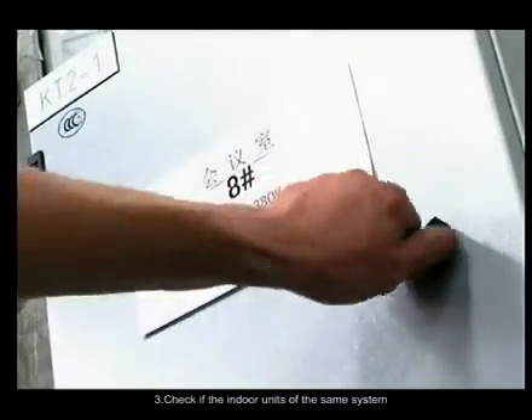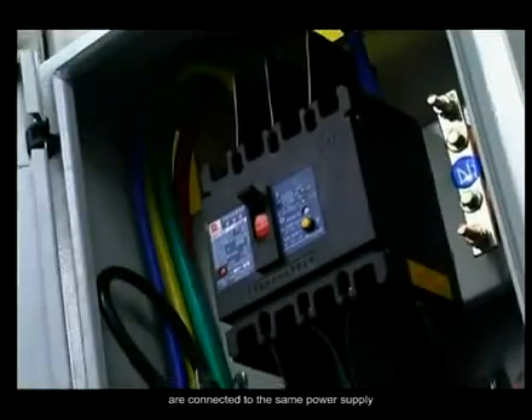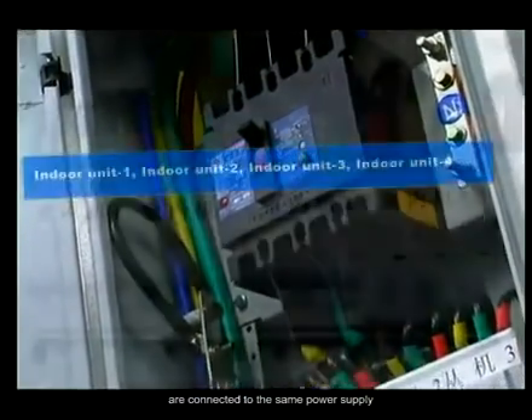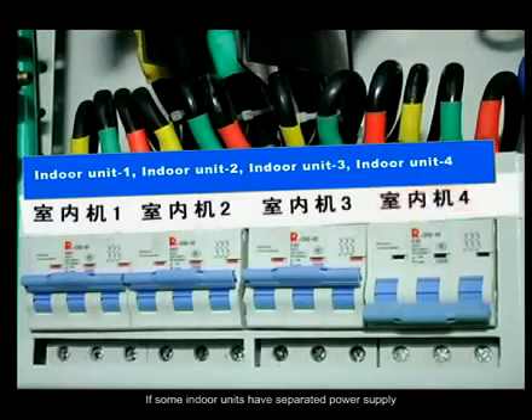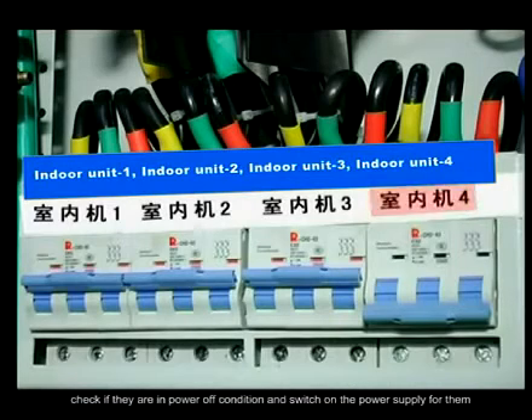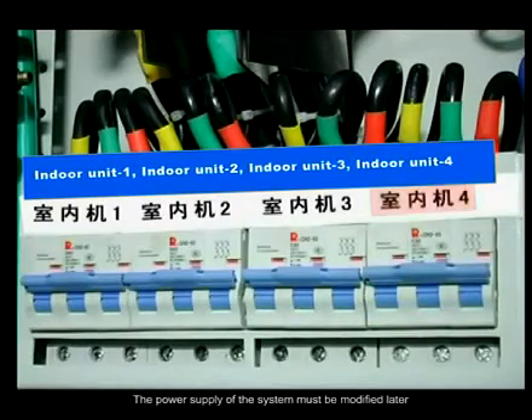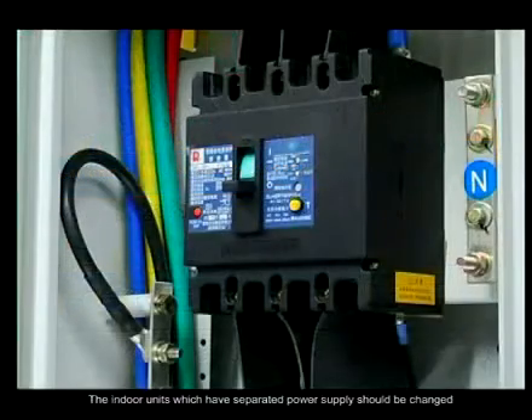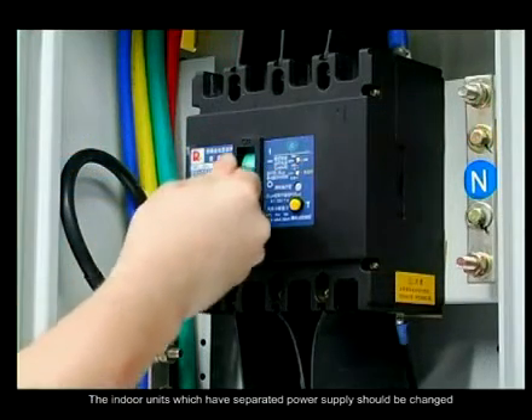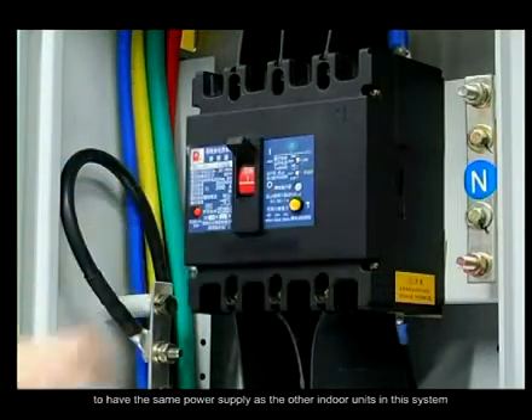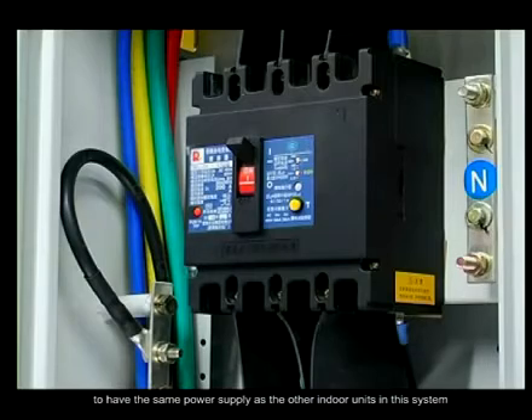3. Check if the indoor units of the same system are connected to the same power supply. If some indoor units have a separate power supply, check if they are in power off condition and switch on the power supply for them. The power supply of the system must be modified later. The indoor units which have a separate power supply should be changed to have the same power supply as the other indoor units in this system.